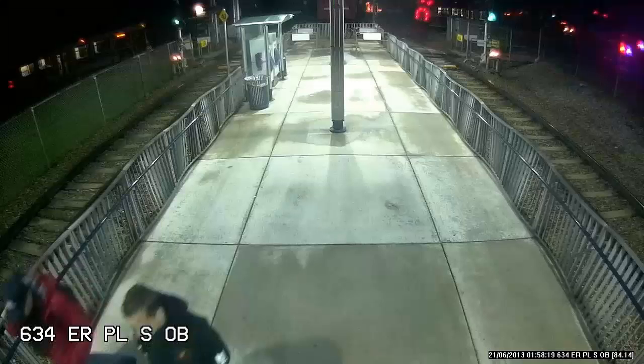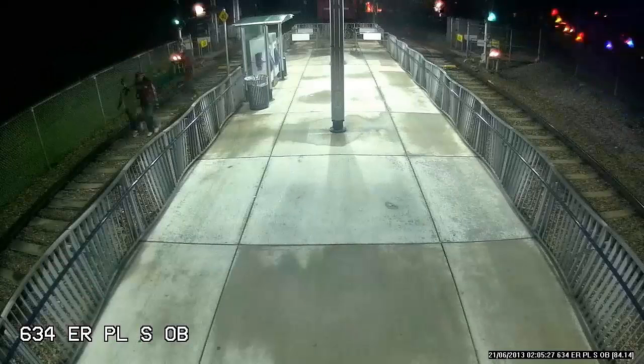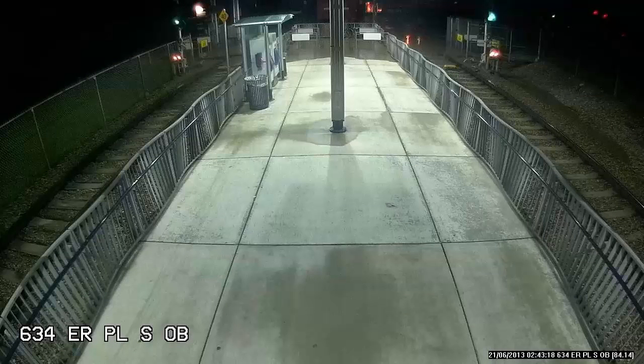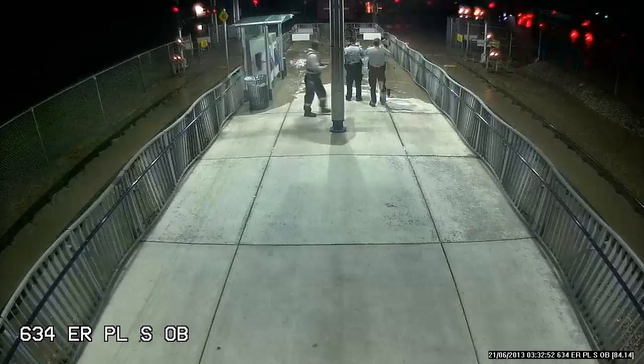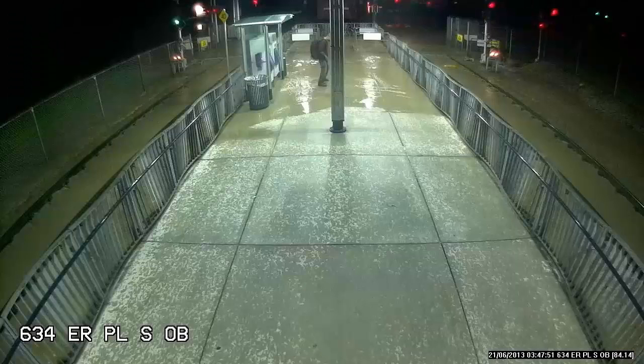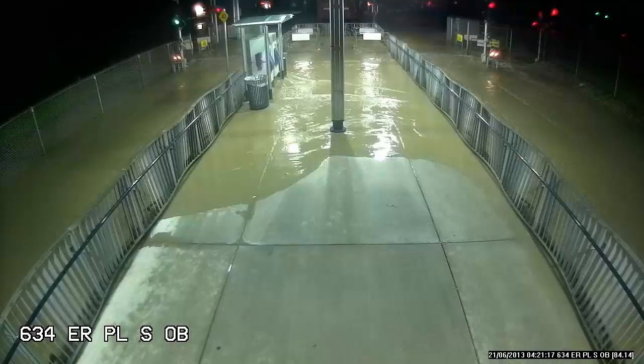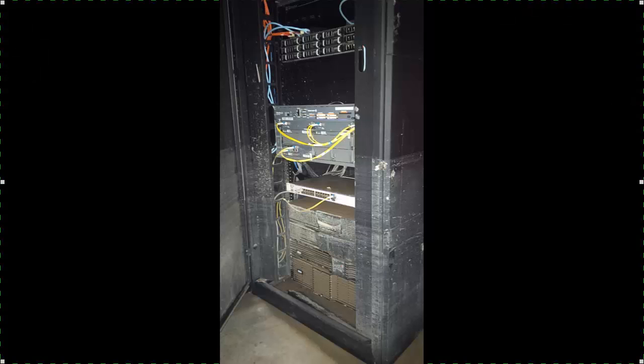Over time, the water crept up this transit platform, and as it crept up, we started seeing failures. So that status board that we were watching started going from green to red, and there we could see that the network elements, the peripherals, were starting to fail. Then finally, all the cameras went down, and as you can see in this picture, the UPS and the switches had definitely failed.